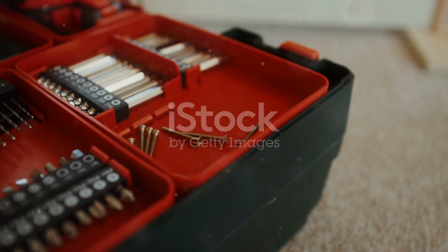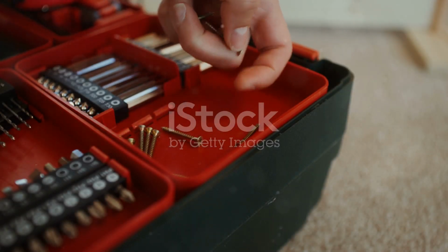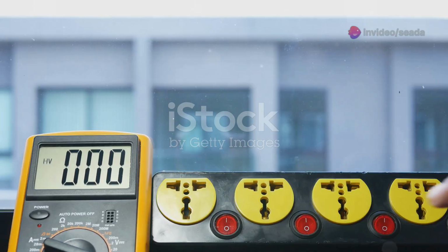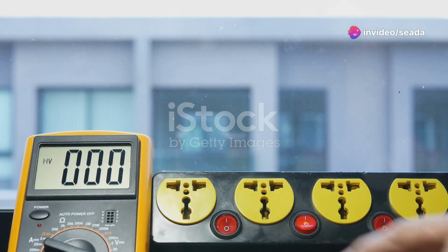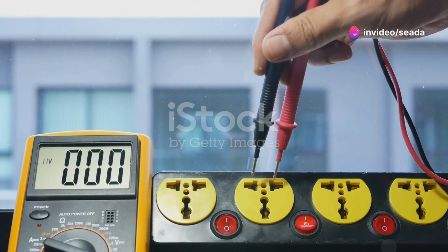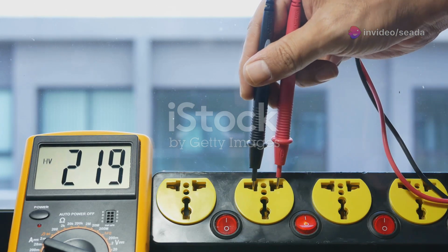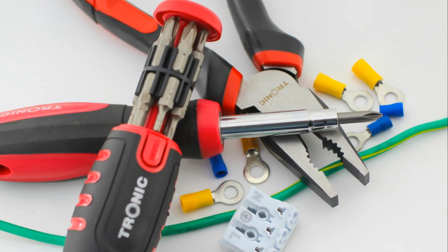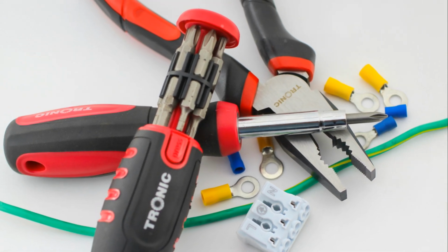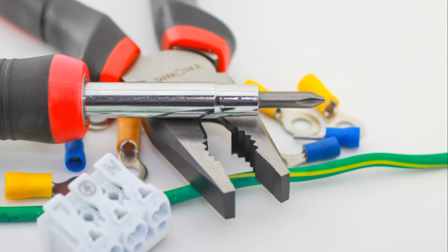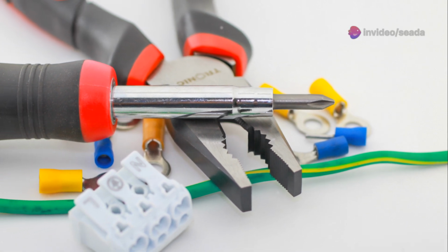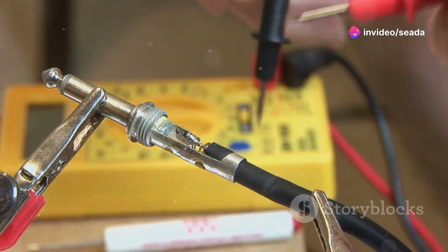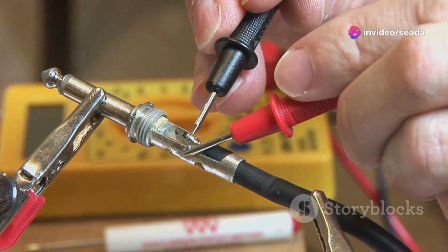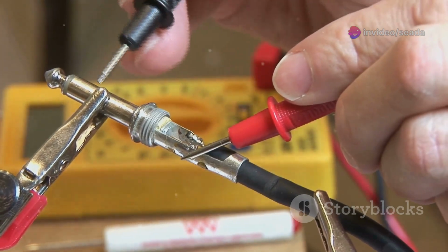The right tools are essential, and using the wrong ones is dangerous. Your top tool is a quality digital multimeter for measuring voltage, continuity, and resistance. Invest in VDE-rated insulated screwdrivers and pliers. These protect you from accidental contact with live parts. A non-contact voltage tester is a quick way to check if a wire is live.